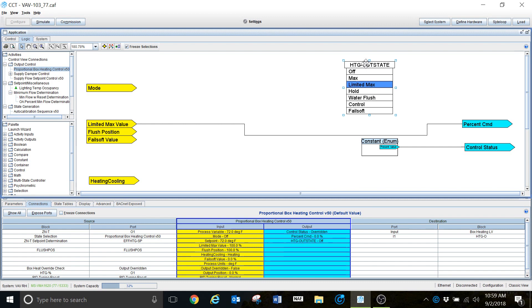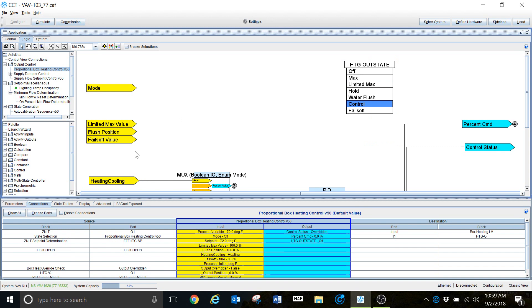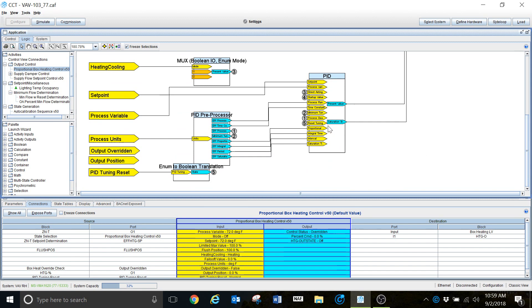This is all controlled by the mode input to this logic block. This mode input is going to come from another logic block further out in the control process. When I click on the Control section, you can see more logic here. This is the PID loop when the VAV is occupied, when it's just trying to control its own set point. This is state-based control — it has its own individual logic block for the particular state within that controller. We have a PID preprocessor, the PID loop control, heating, cooling — that depends on the mode of the VAV. The process variable is the zone temperature.